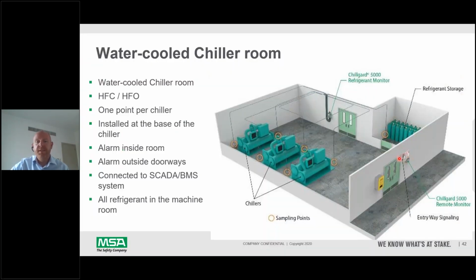So for a typical water-cooled chiller room, in this example we have three large centrifugal chillers, but I have some plant rooms in the Middle East where they have 16 or 17 large centrifugal chillers. So they're big plant rooms. The detectors should always be at the base of the chiller if it's an HFC, because if there's a leak, the leak will always go to the ground. So the base of the chiller is where the leak is going to happen.